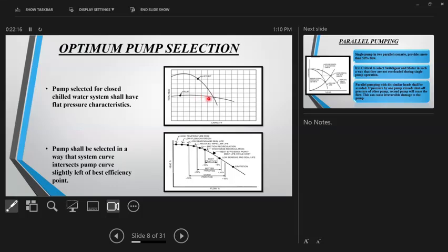The variation in flow is relative, because in a system you are not going to get constant flow in any case. Some valves are going to close, some valves are going to open, a few AHUs are going to close. So variable flow is a reality, and that should not affect your pressures. That's why the flat pressure curve is what is recommended by AECOM.